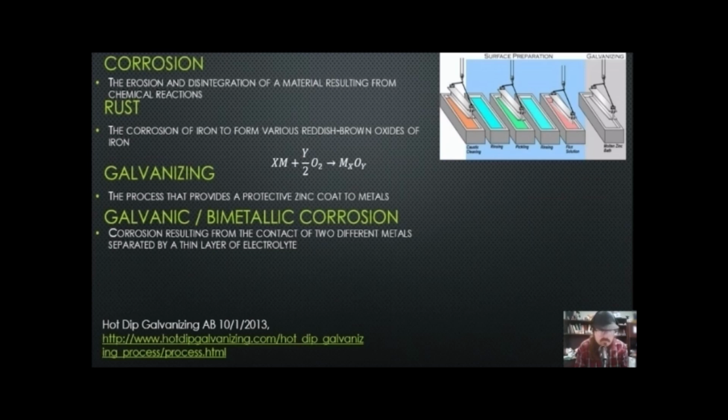And even if the zinc coating is lost in certain places, you get certain holes, maybe someone runs into the thing, maybe you damage it, whatever reason, zinc will still act as a sacrificial electrode to prevent the oxidation of the interior metal until all the zinc has rusted.